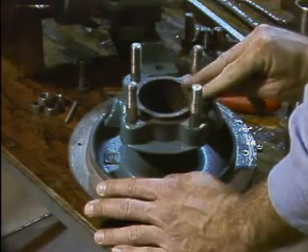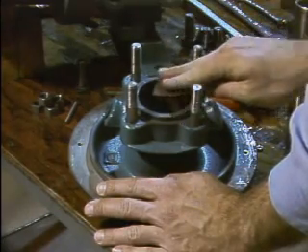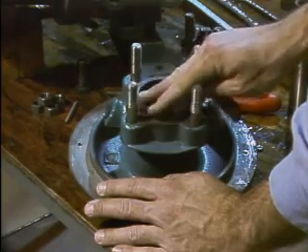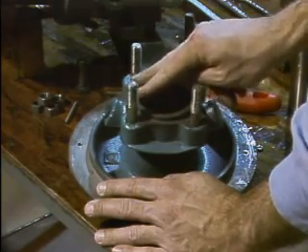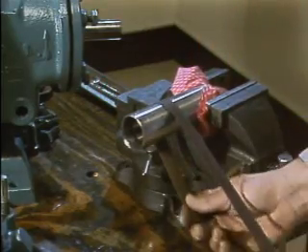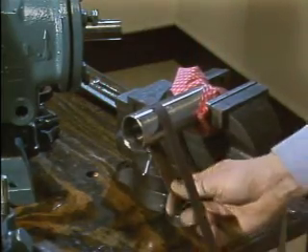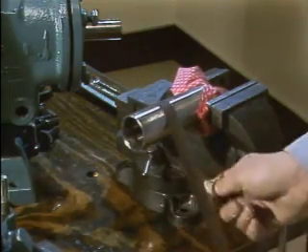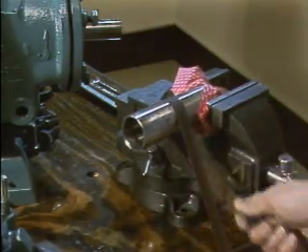One of the first things to do is to check all machined surfaces for nicks and burrs. Minor imperfections can usually be removed with a light abrasive. Defects on the machined surfaces of the frame, the gland plate, the stuffing box housing, the shaft, or the sleeve could result in leaks and damaged components.